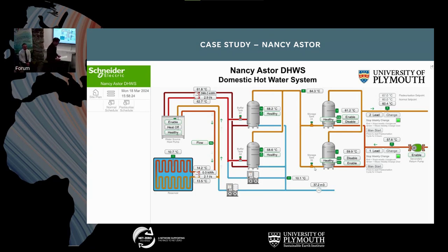Now, probably the biggest design challenge for us was to ensure we met the university's water compliance code of practice for stored hot water temperatures and distribution. This was challenging because the employer's requirements didn't lend themselves to the use of a high temperature heat pump, meaning at design stage we had to assume a worst case scenario of a 55 degree achievable temperature from the renewable source alone. Although higher seasonal temperatures were expected, we couldn't rely on this at that stage.